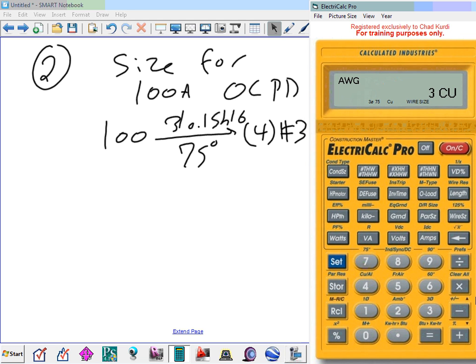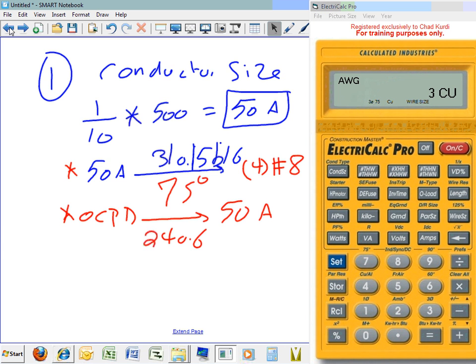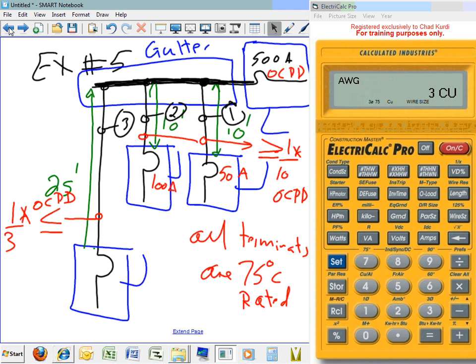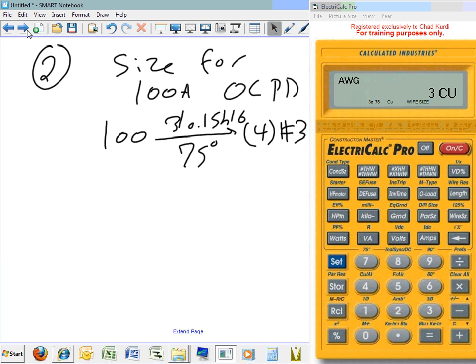Any questions about that? The last thing before I let you go eat is the 25 foot. Let's do the 25, right? We did these two. I hope you understand, guys, when I did these, this one was the minimum that I can use. This one was more than the minimum. That's okay. My minimum conductor size, guys, came up with number 8. But can I tap number 3 if my minimum is number 8? Duh, Chad, of course. Number 8.